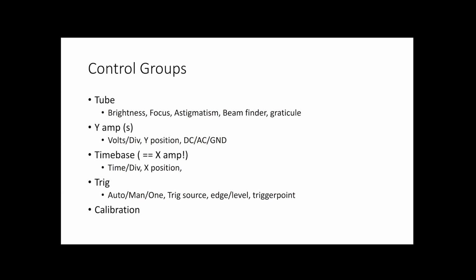So that's us finished with the control groups. The tube control group contains brightness, focus, astigmatism, brightening up the scales, the graticule, and a thing called the beam finder. If you've got an old analog scope, there'll be a button on it called the beam finder. And what that does is it turns the beam on, it turns down the Y amplifier, it turns down the X amplifier, and puts the beam on the screen so that you can see it, so that you know that your scope's working, and so that you know where it's flashing off to, what's turned up too high. And the beam finder's a great thing. You press the button and the beam appears and you know that your scope's working and you've made a mess of something.